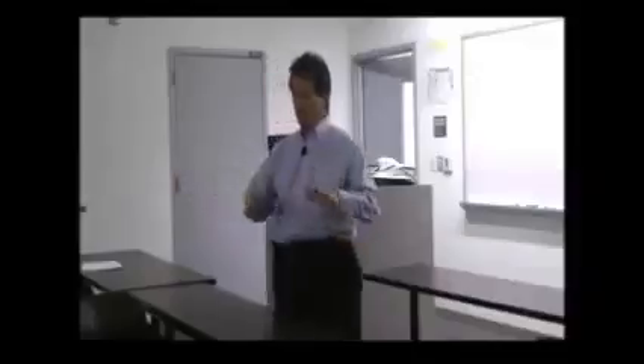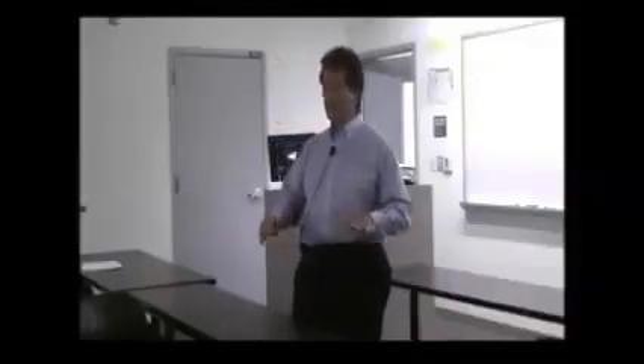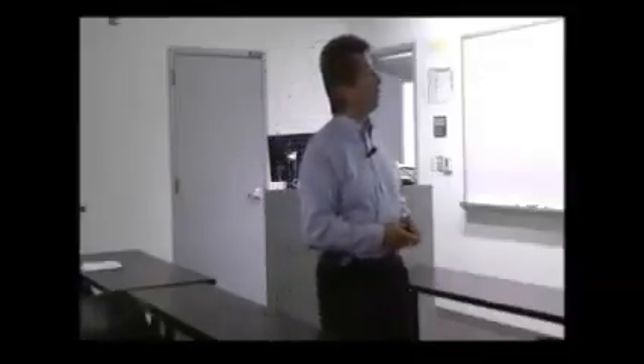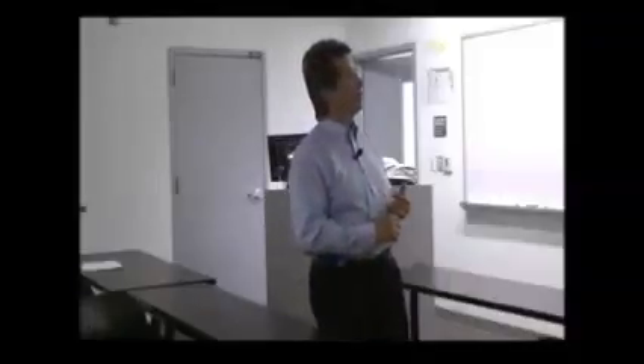Okay. Some operational initiatives. Use demand control ventilation. Use it only when you require it, such as an auditorium. If it's empty, I'm cycling it way down. I'm not using outside air or introducing additional cooling or heating. But as I start to fill it up, it makes the adjustments, so demand control. Okay. Higher efficiency air filters, depending on the application. Ultraviolet lights near air conditioning.